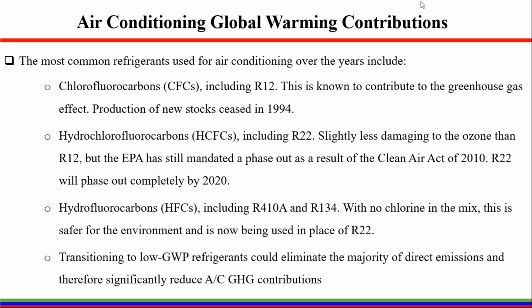Hydrofluorocarbons that include R410A and R134a have no chlorine in the mix. This is safer for the environment, and R410A is currently being used in the most efficient air conditioning systems in place of R22. Transition to low global warming potential refrigerants can eliminate the majority of the direct emissions and can significantly reduce the air conditioning based greenhouse gas emissions.